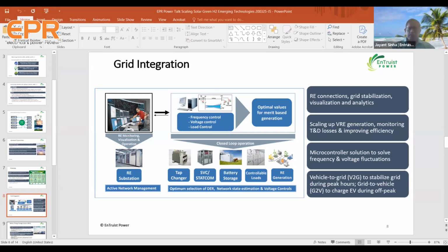From the distribution side, we already use certain mechanisms: when distribution voltage becomes high, we have on-load tap changers, and if reactive power is high, we have STATCOMs and synchronous voltage condensers.